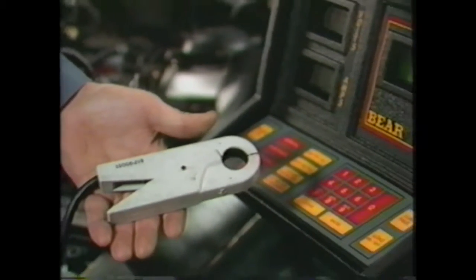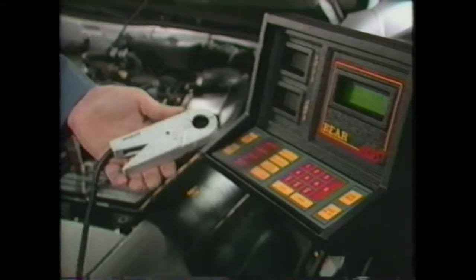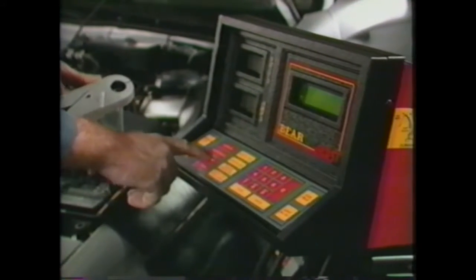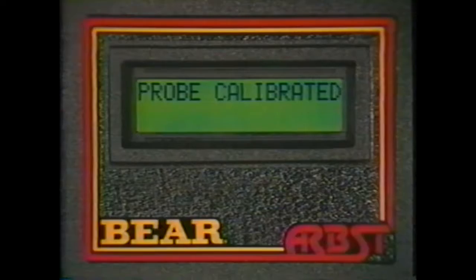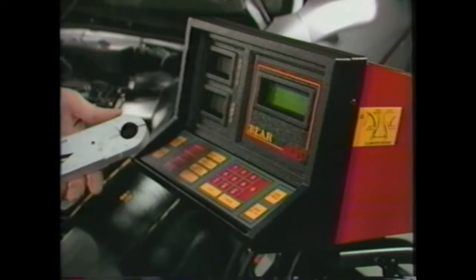First, make sure the amps probe is disconnected and held away from any electrical conductor. Also, be sure the clamp is closed. Then, press the 0 amps key on the console. The display says probe calibrated. This probe is zeroed. That's all there is to it.